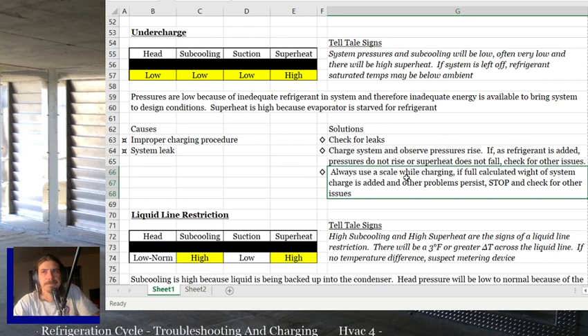But the bottom line is most of these problems, if it affects the suction side, the evaporator side of the system, if you have a TXV, a TXV might skew the readings closer to normal. So you've got to be a little bit more wary of what the TXV is doing, if the TXV is hunting.